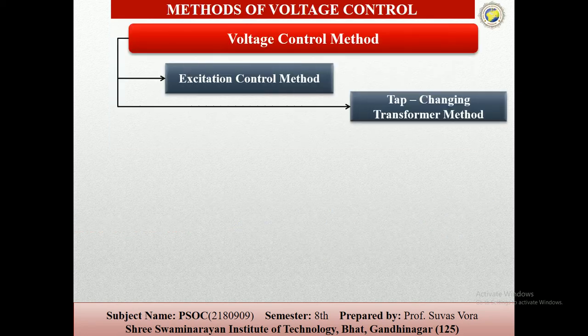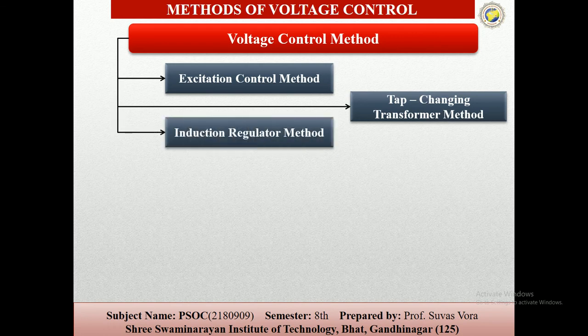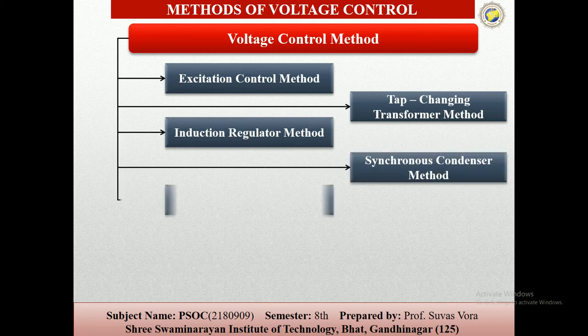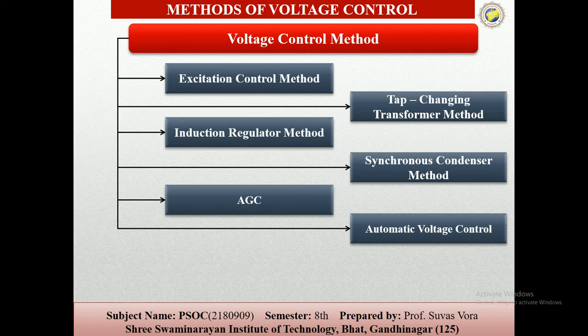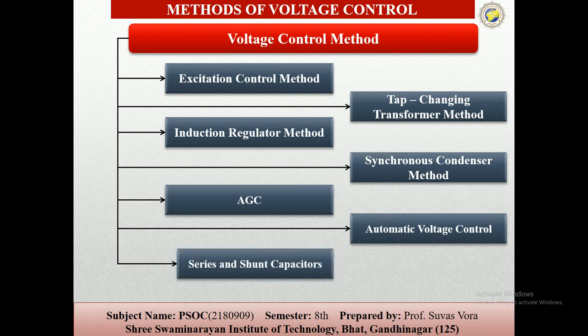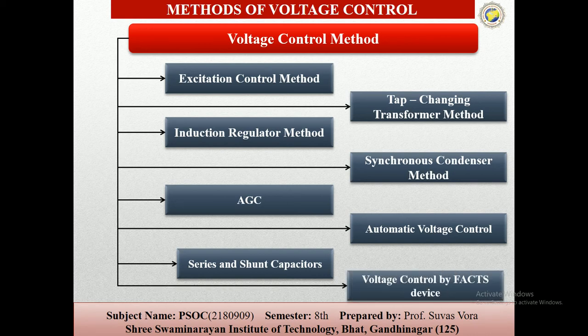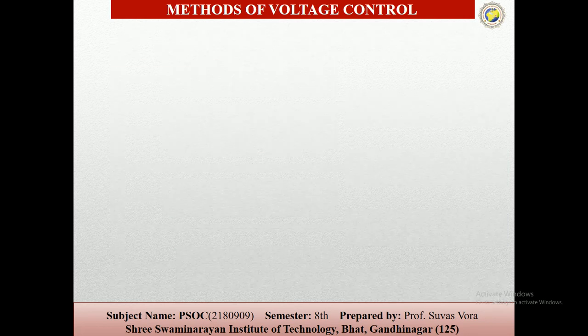So we have already seen the excitation control method and the tap changing transformer method. Now the induction regulator method, synchronous condenser method, AGC method, automatic voltage control, series and shunt capacitors, and voltage control by the FACTS devices. So now the induction regulators. In an induction regulator, one winding is moved with respect to the other winding, and depending on the flux cut, the secondary voltage varies. The primary winding is connected in parallel with the supply and the secondary winding is connected in series with the transmission line.